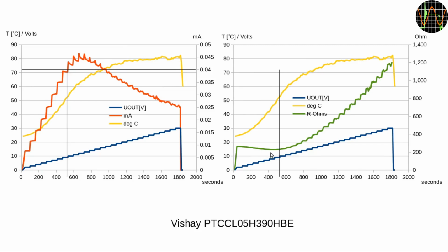As the current jumps up after each voltage increase, the PTC heats up more and increases the resistance, and that increase is more than would be needed to keep the current steady. It increases by so much that the current actually drops. This causes these spikes. Once a maximum of slightly above 45 milliamps is reached, the further increases in voltages cause so much increased resistance that the current now drops. It falls even well below the initial trip current, but of course the PTC is now very hot, above 80 degrees Celsius or so, it does not matter.